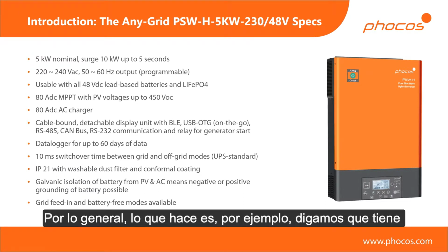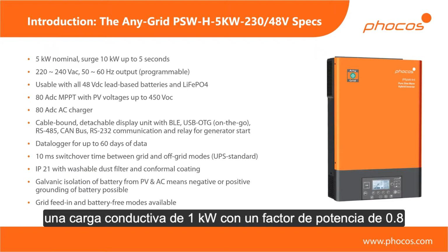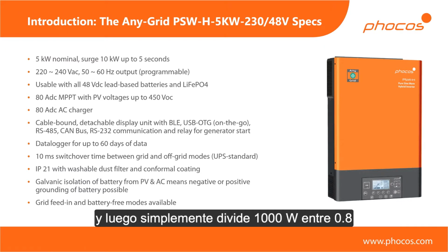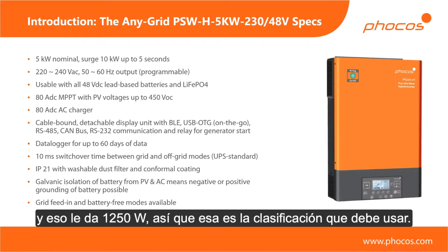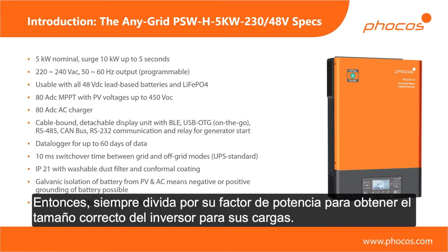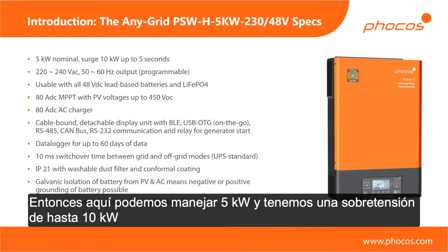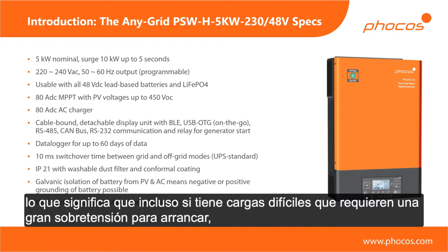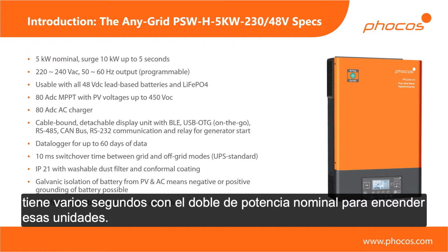So typically what you do is, for example, let's say you have a 1 kilowatt inductive load with a power factor of 0.8. Well, then you simply divide 1,000 watts by 0.8, and that gives you 1,250 watts. So that's the rating you should be using. So you always divide by your power factor to get the correct inverter size for your loads. So here we can handle 5 kilowatts, and we have a surge rating up to 10 kilowatts. So it means that even if you have difficult loads which take a large surge to start up, you have several seconds with twice the nominal power to get those units started up.